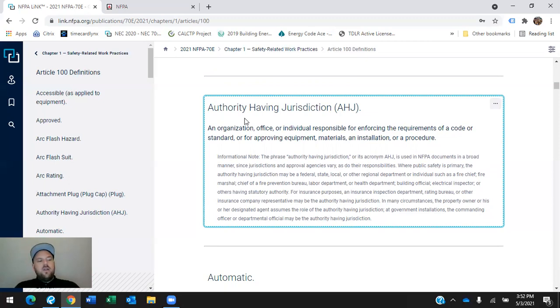Sometimes inspectors come out with these pet peeves, one little thing they always focus on. At that job I was at, the guy didn't want any MC sitting on top of the ducts - that was it, he didn't care about the strapping. As I was walking with the inspector, I noticed sections of MC 16 feet long that didn't have a strap on, and I'm fuming inside because my guys didn't follow that simple rule. But he looked right at it, turned around, went around the corner, found a piece of MC laying on top of the duct, and called us on that one instead.